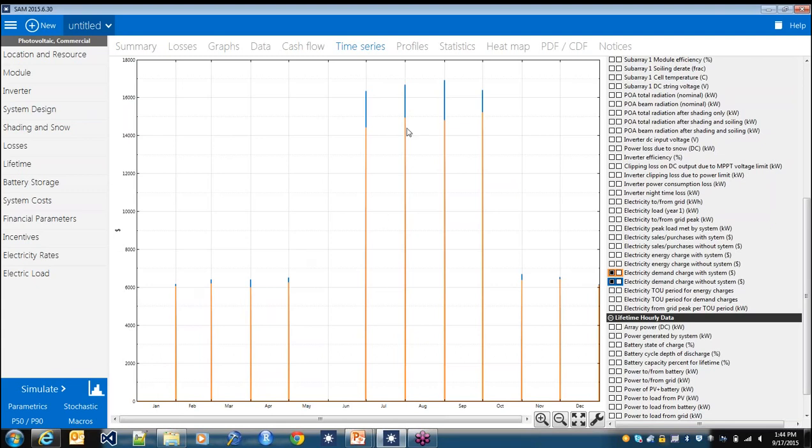And so you can see here that over this period of time that we put the battery controller on, we actually are reducing our demand charge by several $1,000s a month. And so you can imagine that as you spend more time carefully tailoring that schedule, you can start to chip away at that demand charge.